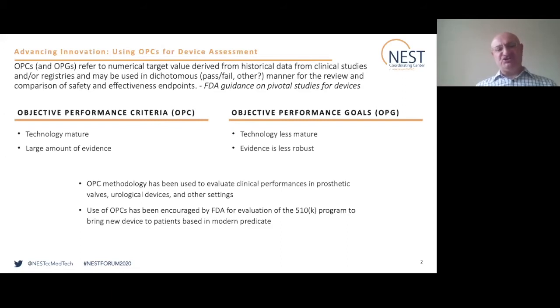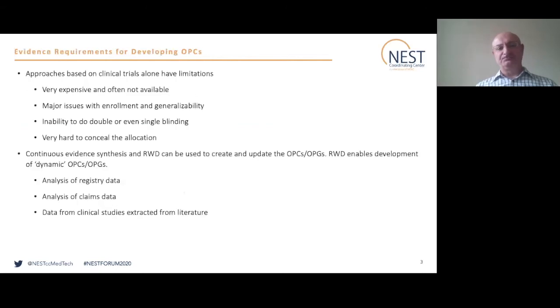In the past, OPC methodology has been used to evaluate clinical performance of prosthetic valves and urological devices, and FDA has experience of using this methodology for evaluation of device submissions at the pre-market, and also evaluation of devices in a post-marketing setting. We think that since the launch of the real-world evidence guidance, FDA is encouraging use of objective performance criteria as one of the tools possibly that can be used for a 510(k) program as well.